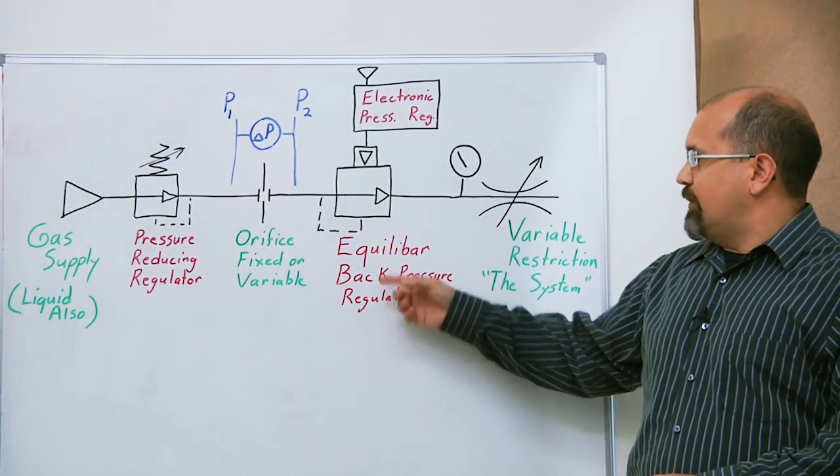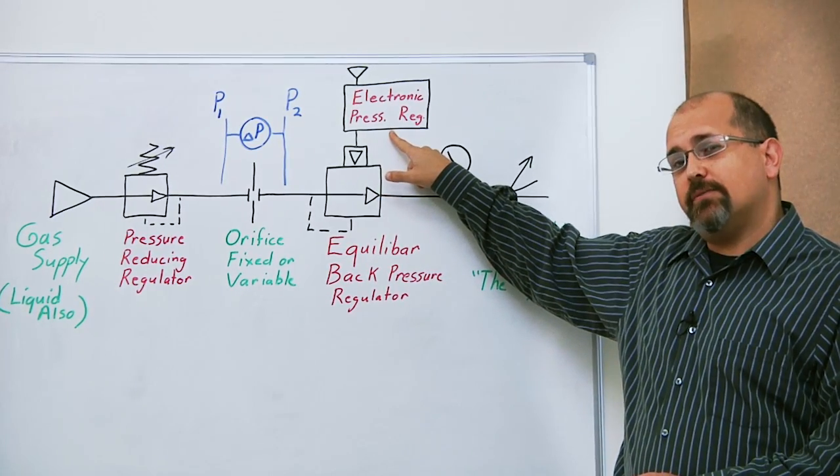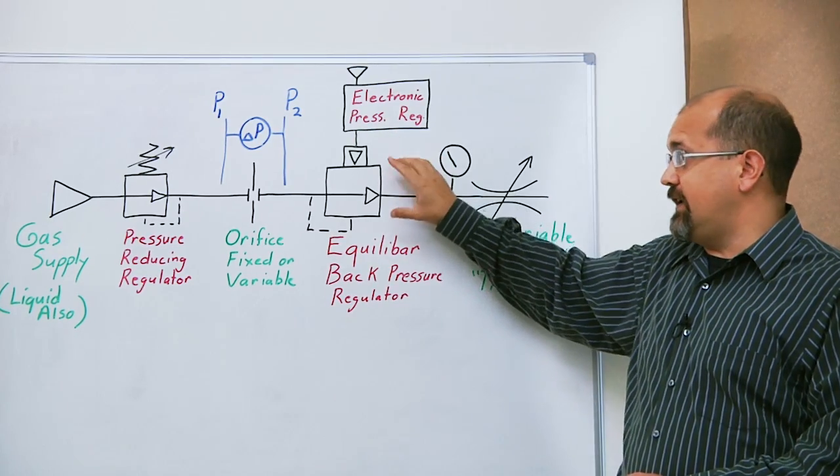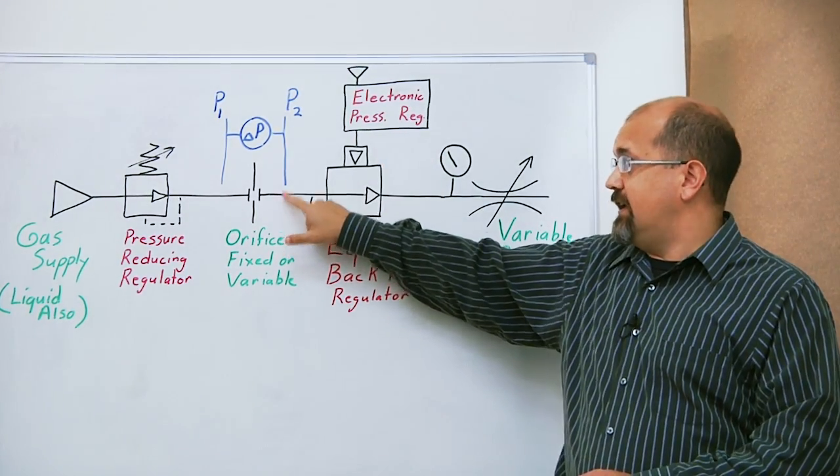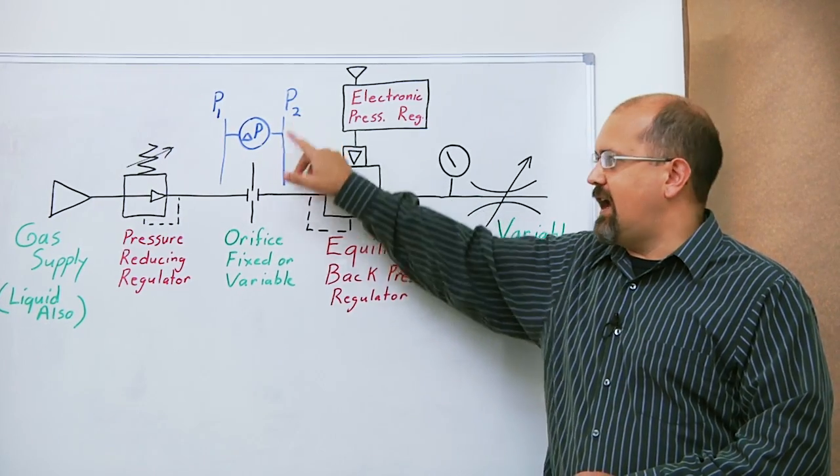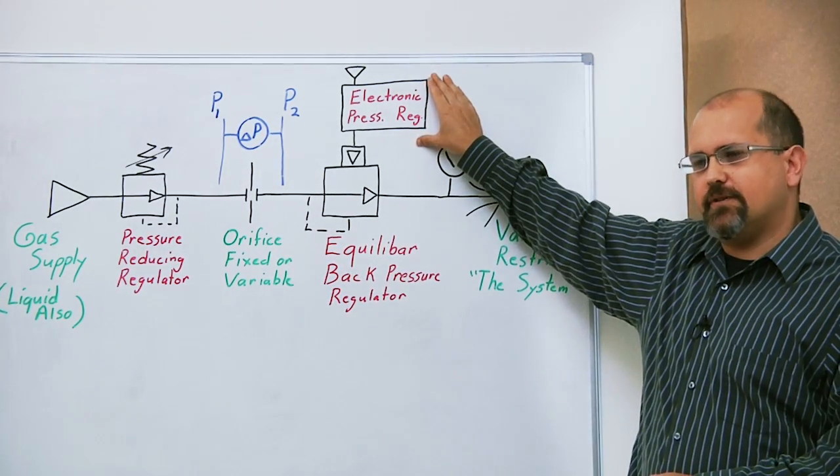The Equilibar regulator is pilot operated by an electronic pressure regulator. This electronic pressure regulator lets me vary the command setpoint to the Equilibar and therefore vary the P2. By varying P2, I can control the differential pressure across the orifice using the electronic pressure regulator.